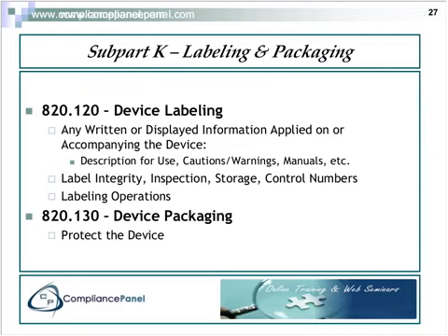Subpart K deals with labeling and packaging. This has an interesting twist, because when we think of labeling, we think of stickers and other labels that are applied directly to the product or its packaging. The twist is that labeling, as seen through the eyes of the FDA, is any written or displayed information which could be accompanying your device, or it could be product brochures, or it could be information that's on your website.